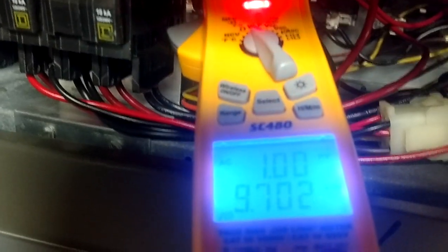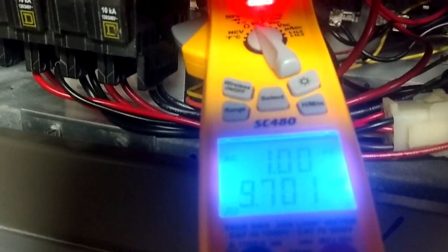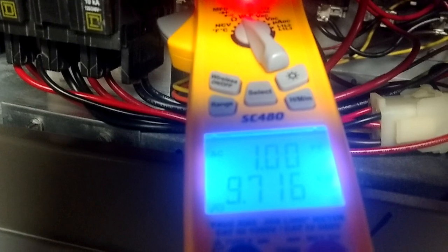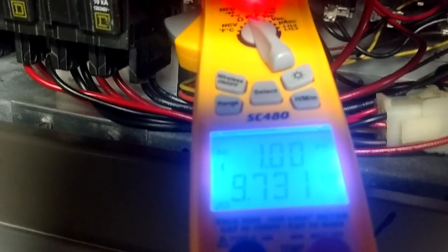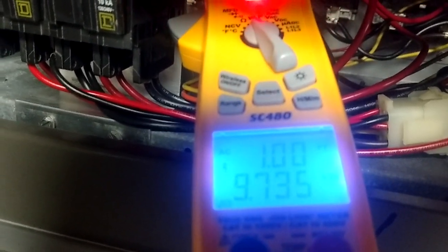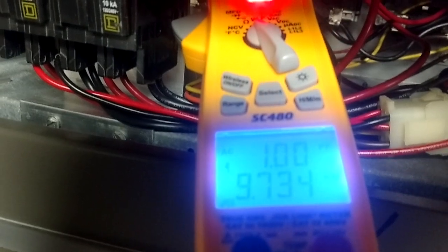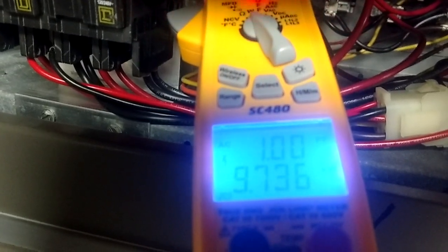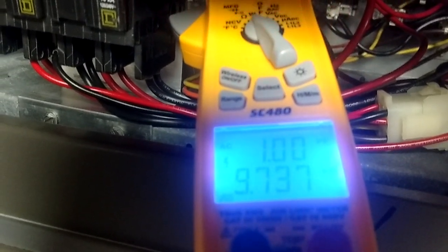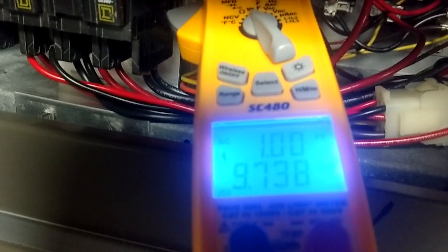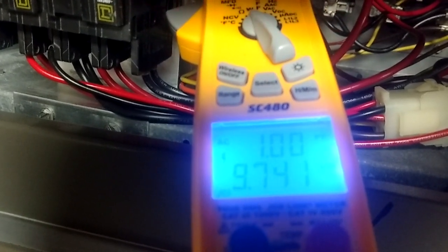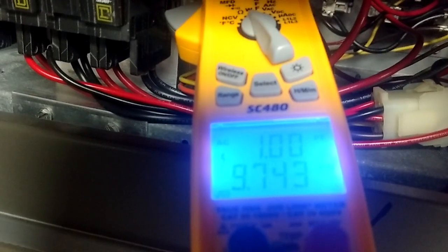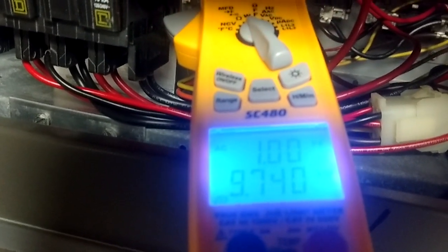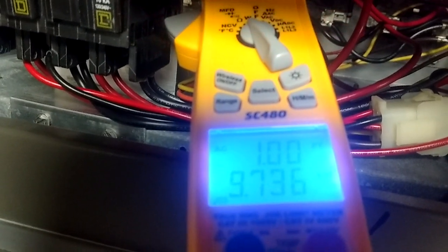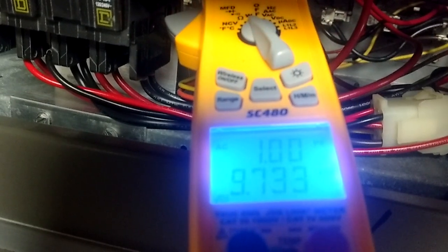And Fieldpiece has done a really good job with watts here because they've utilized the dual display. The top line is our power factor, so we have a power factor of 1. And then you see down there on the bottom, like we were talking about, we're at 9.73 kilowatts. So that's right there at our 10 kilowatts that we are expecting on that 60 amp breaker.